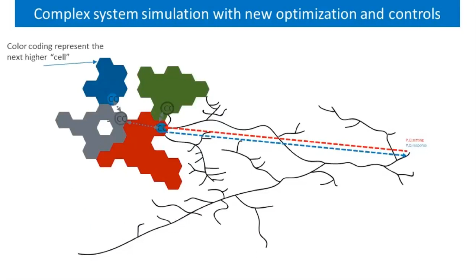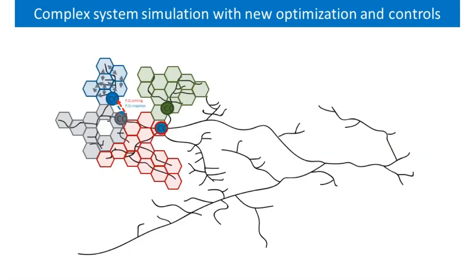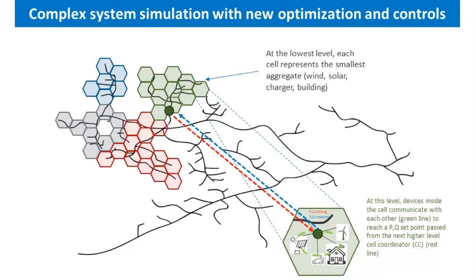Now we want to look at how we apply this to grid applications. Here we're looking at a single distribution circuit, looking at how we could send P and Q, real and reactive power set points, from a substation down to the distribution system, setting them into different cells.